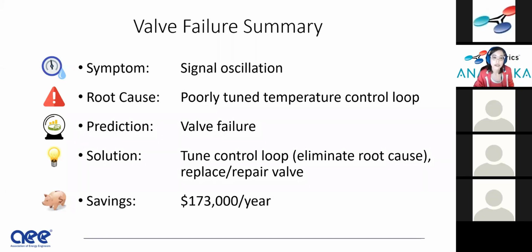The root cause here is a poorly tuned temperature control loop. Sometimes it can be set points, as I mentioned. What we're predicting is the valve failure. We're predicting that the valve's going to fail, and we're going to blow steam, and simultaneous heating and cooling is going to occur, and you could potentially have comfort issues. The solution here is to tune the control loop. That's really eliminating the root cause.